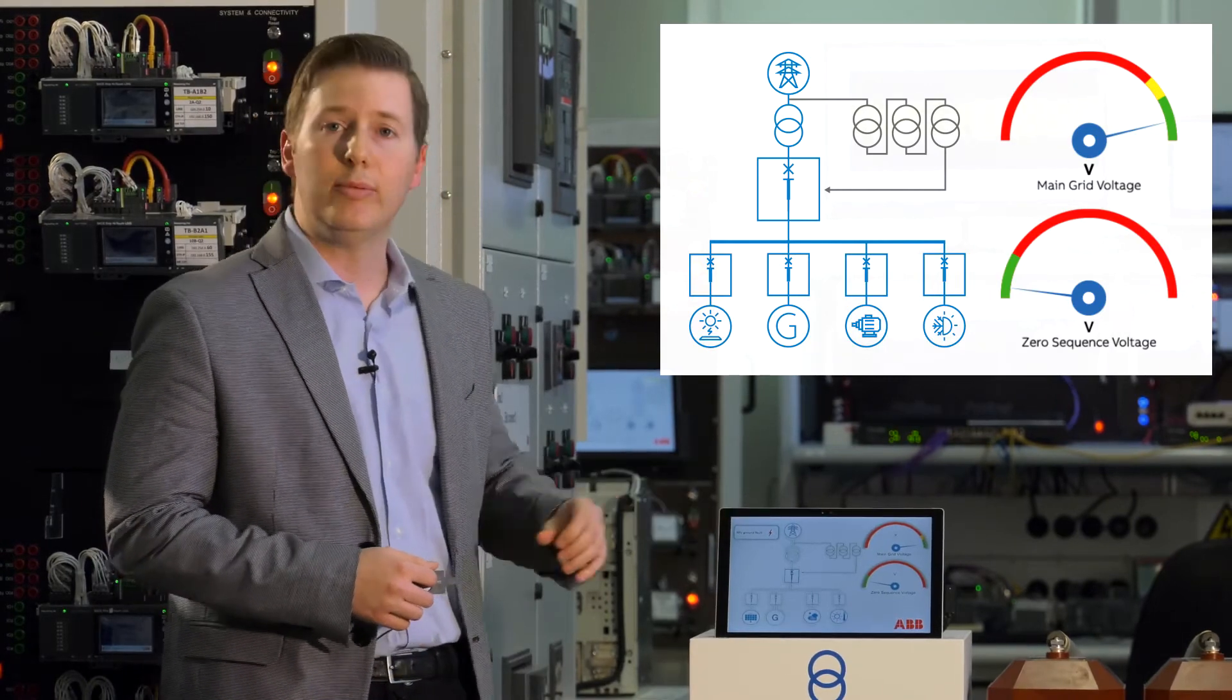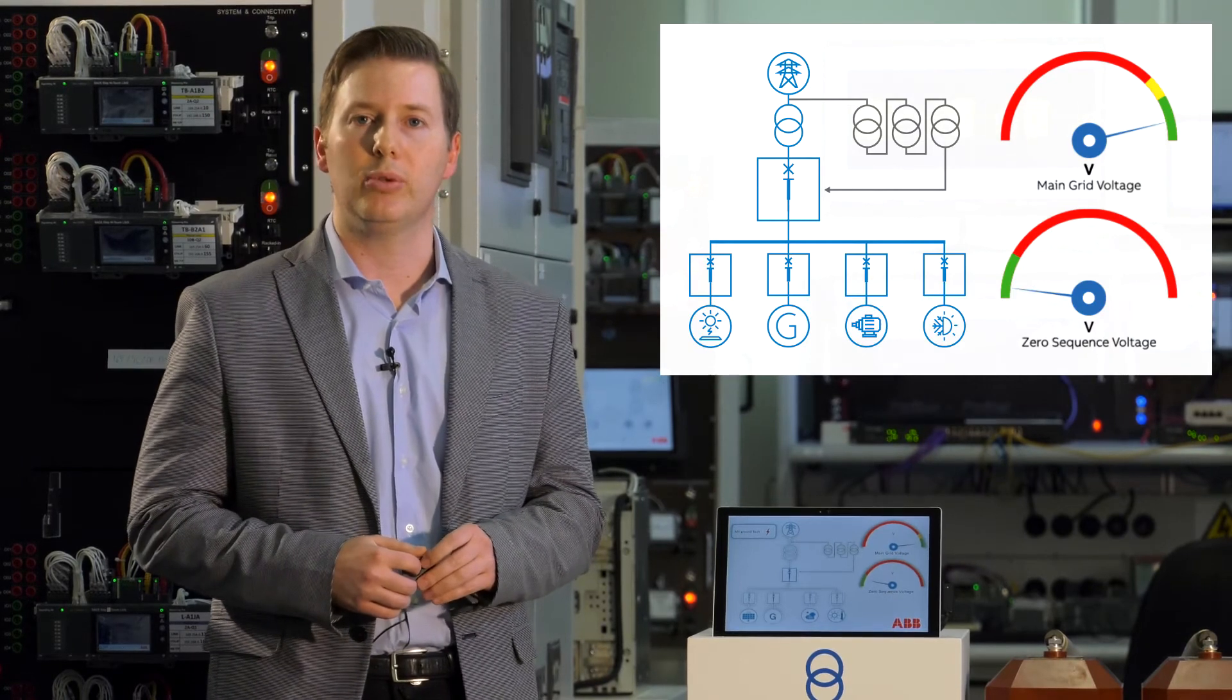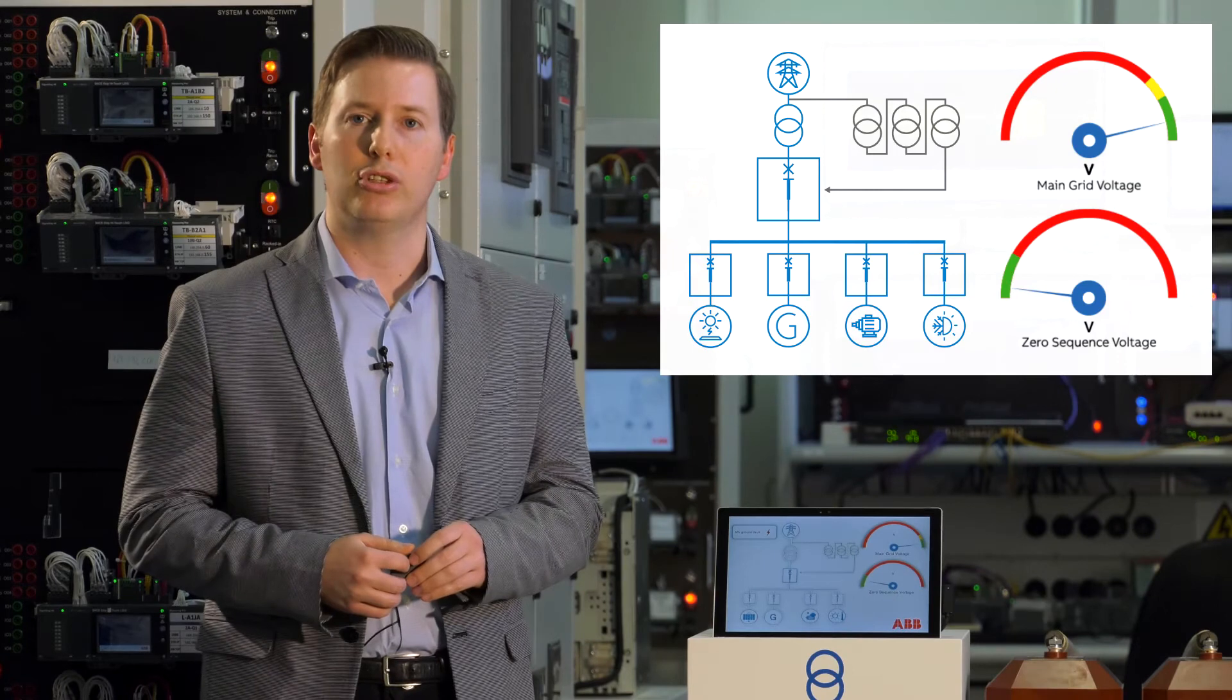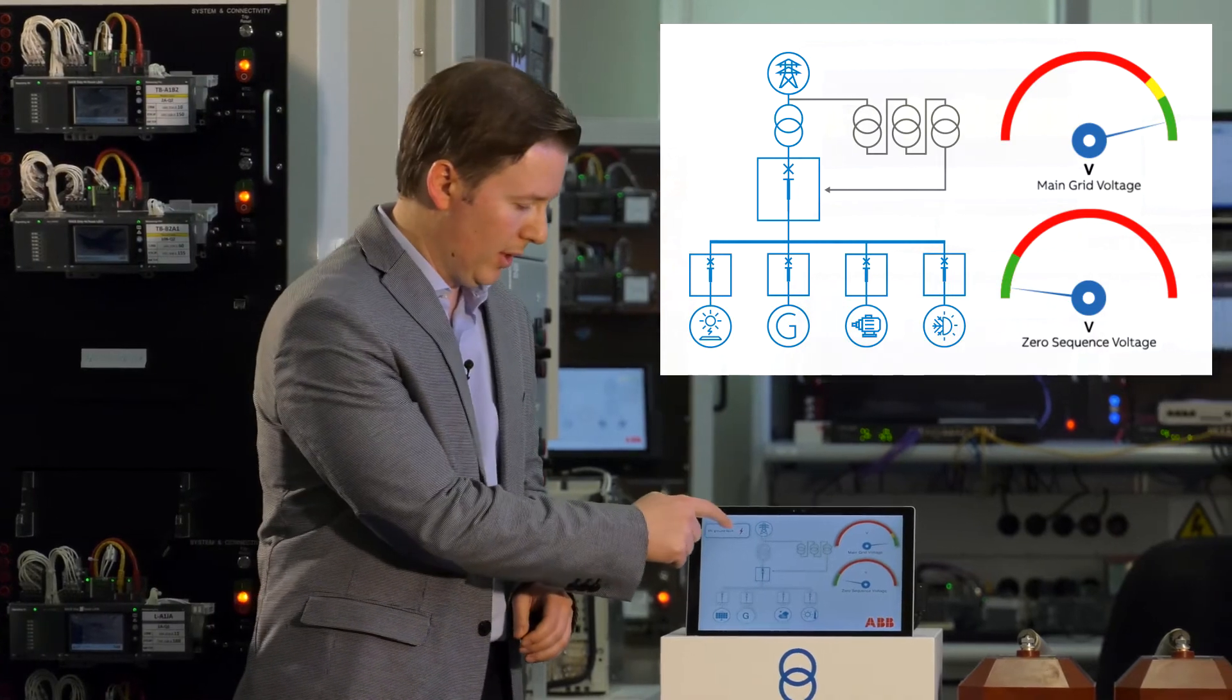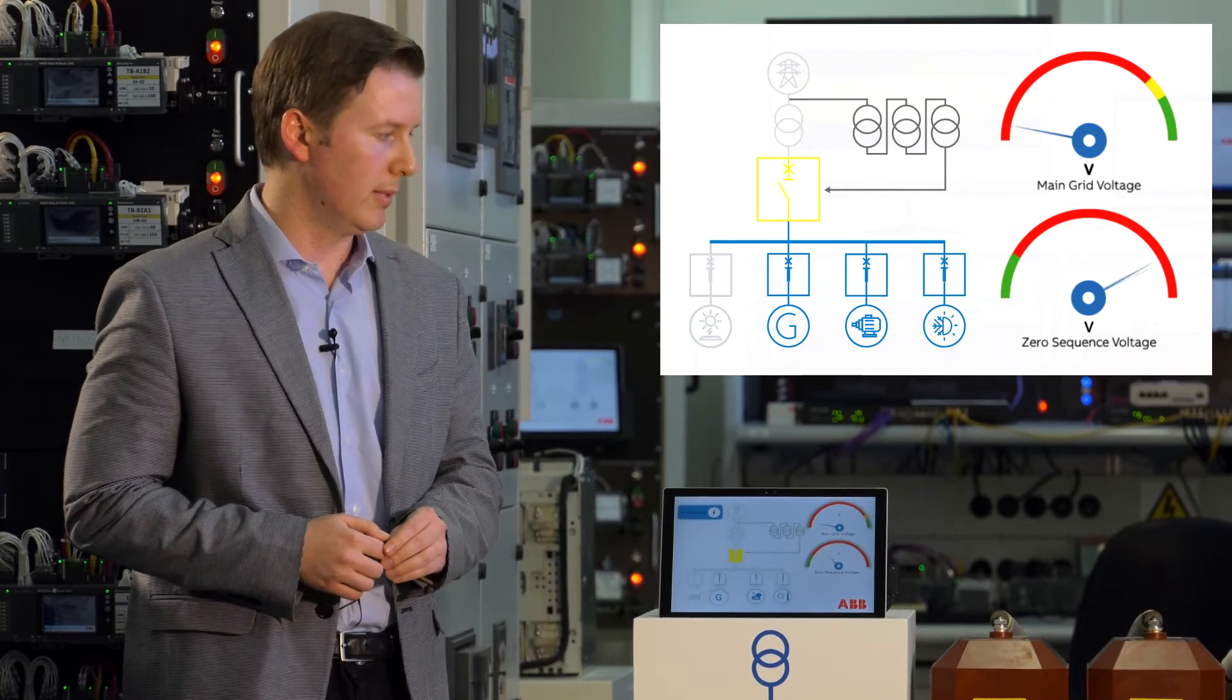If we simulate a medium voltage ground fault thanks to the generation of zero sequence voltage signal, the circuit breaker changes automatically the frequency threshold and trips due to under-frequency. We generate the ground fault. And the circuit breaker has tripped due to under-frequency.